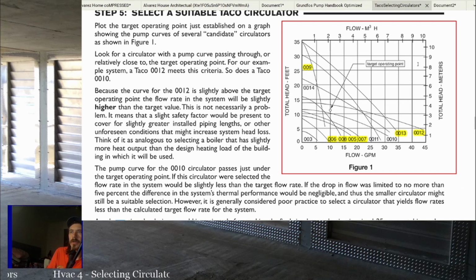So these are all curves for different pumps, and I kind of wish they'd make this thing in different colors to make it easier, but it is what it is. Maybe I'll go through and color this graph one day so it's easier to see, but these are all just different pumps. So you plot the target operating point on the graph showing the pump curves that you're working with, and a lot of times you'll actually pull up the pump curve for just the 007 and the pump curve for just the 0012, or the pump curve for a B&G model, or a Grundfos pump or whatever it is. You'll pull up those pump curves and then you'll look at that curve and put wherever you need that pump to perform on here. All right. So right here, this is the operating point that we're dealing with. Okay. Right there.